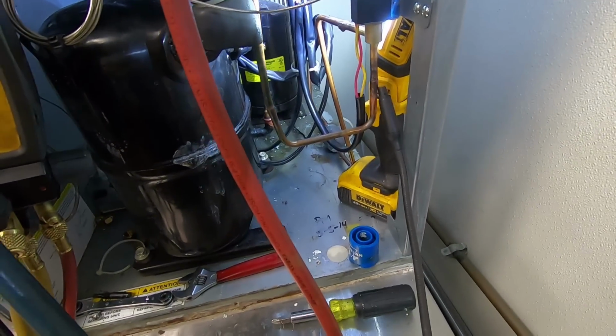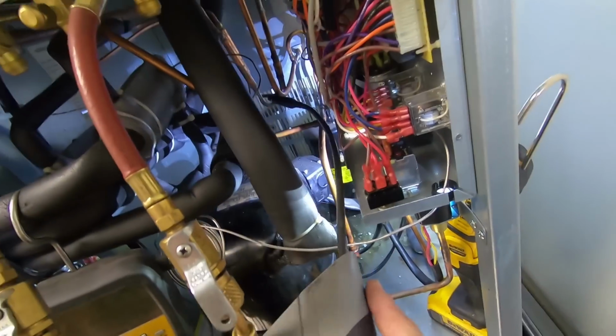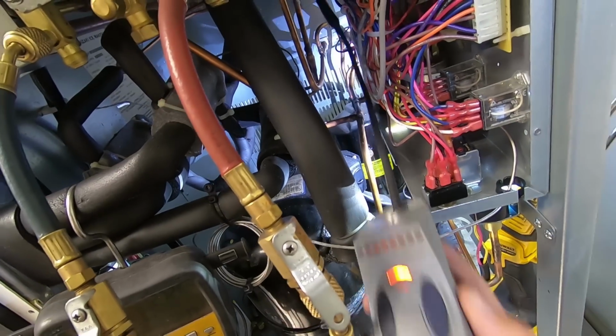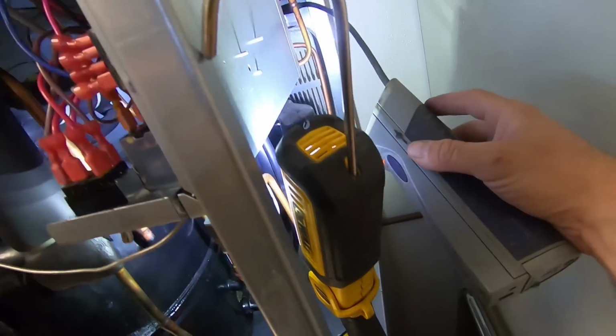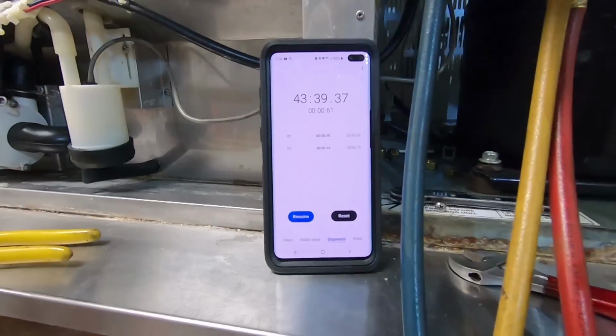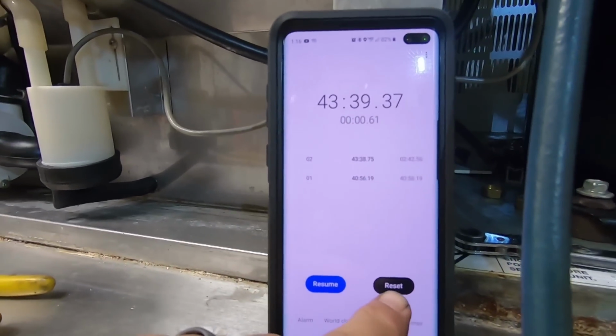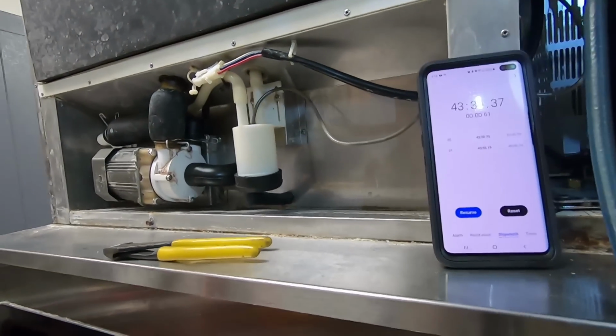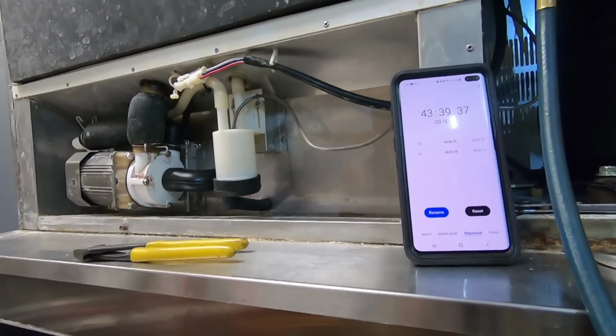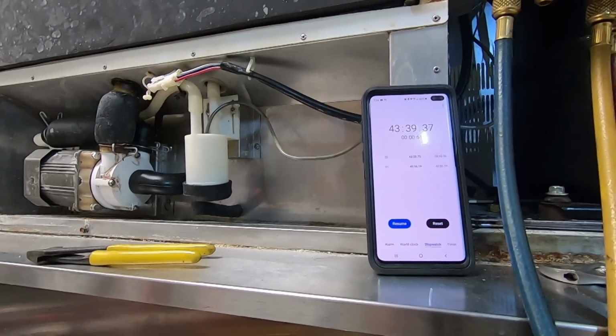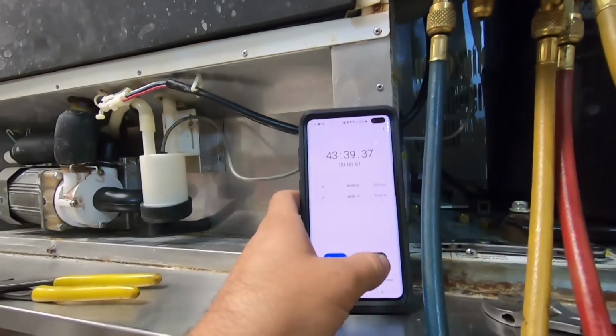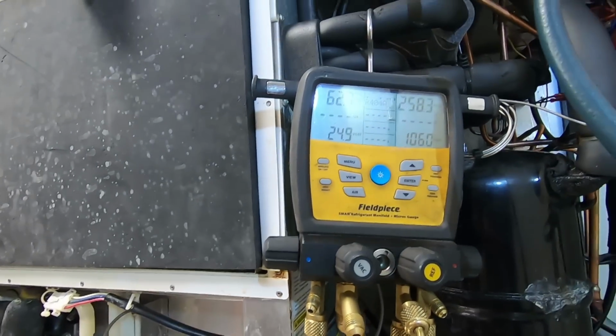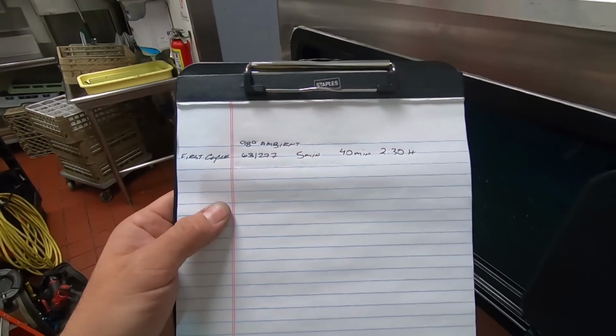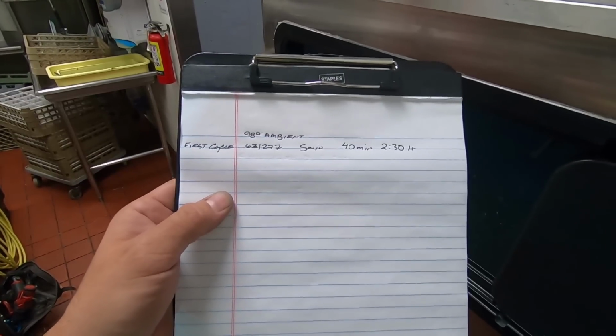All right, so we're going to do a quick leak check. Nothing, just hitting all the welds. Nothing. Check the rest of the machine. Nothing. So we're good. We're just going to let it run. Okay, so we've started our new freeze cycle. So this is what we're at. We'll write those numbers down. So we had a 40-minute freeze and a 2.5-minute harvest. And then we'll hit reset and start. At the 5-minute mark, we'll do this again. Check the pressures, write them down, and make sure we get good ice coming out of this machine, make sure it makes it a couple times before we leave.